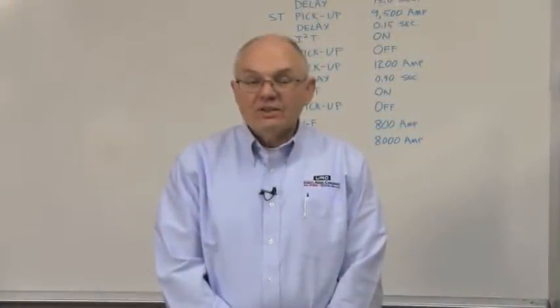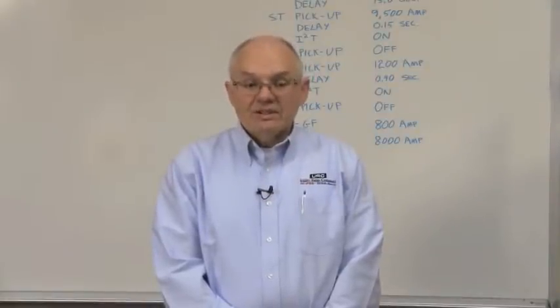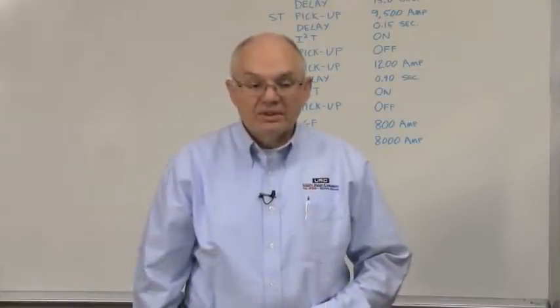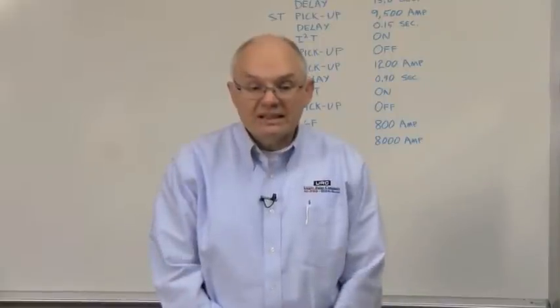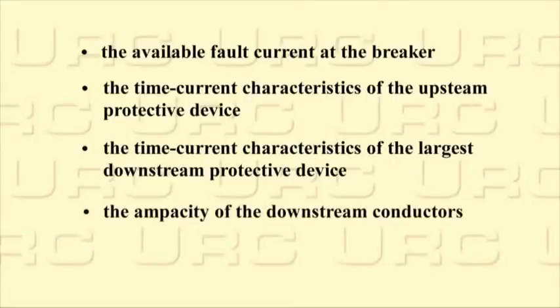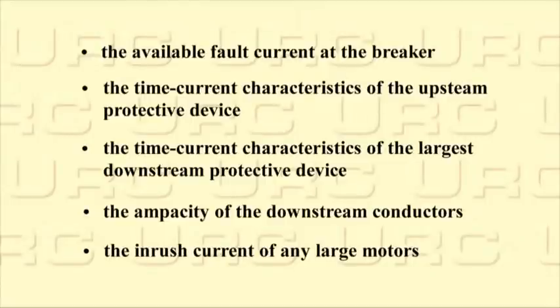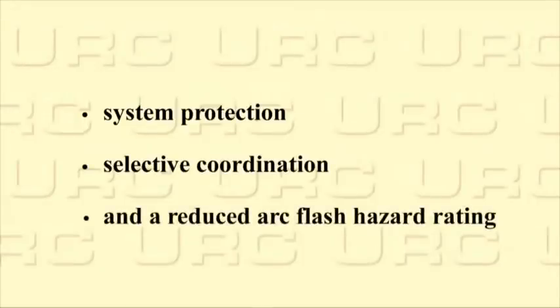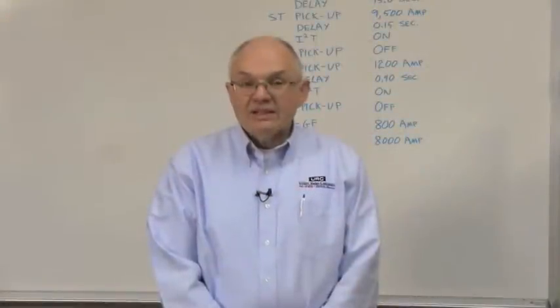Before we get started, I just wanted to go over two commonly asked questions. The first question is: how do I know what the settings should be for the ACPro? The best way to determine the settings is through a coordination study. The coordination study determines the available fault current at the breaker, the time current characteristics of the upstream protective device, the time current characteristics of the largest downstream device, the ampacity of the downstream conductors, and the inrush current of any large motors. With all this information, the settings can be determined that will provide system protection, selective coordination, and also reduced arc flash hazard rating.